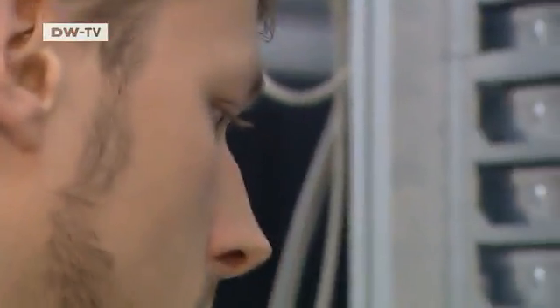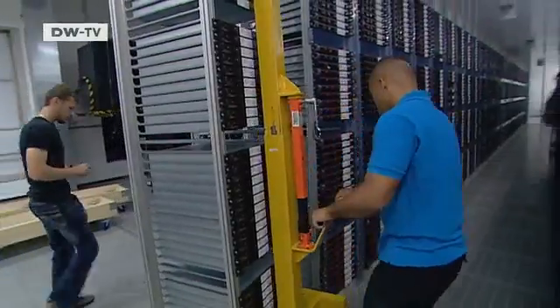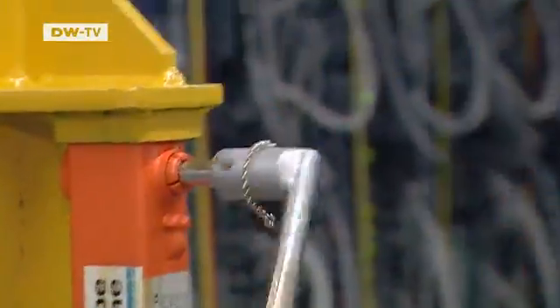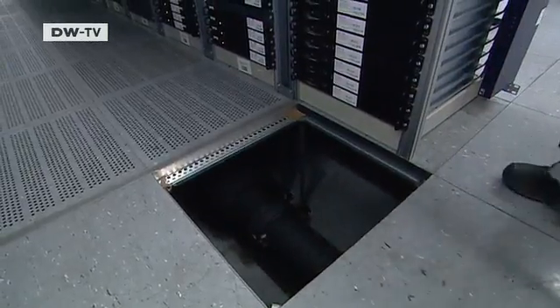The workers are in a hurry. They've opened the cold aisle to install the new racks, and that needs to be done quickly so the cold aisle can be closed again — otherwise it's going to warm up. The cold air comes through the forced convection air cooling units on the wall and is blown in through the double flooring on the cold aisle.